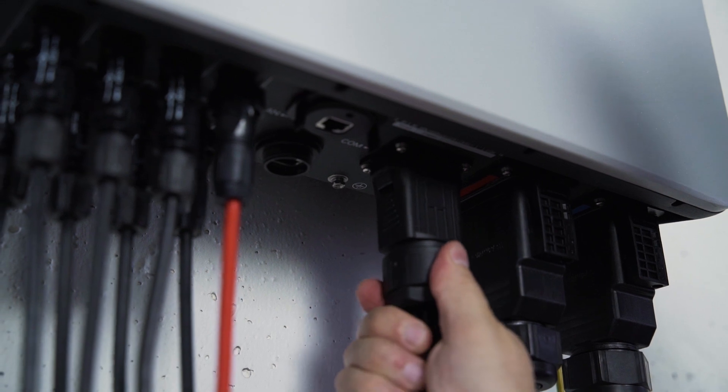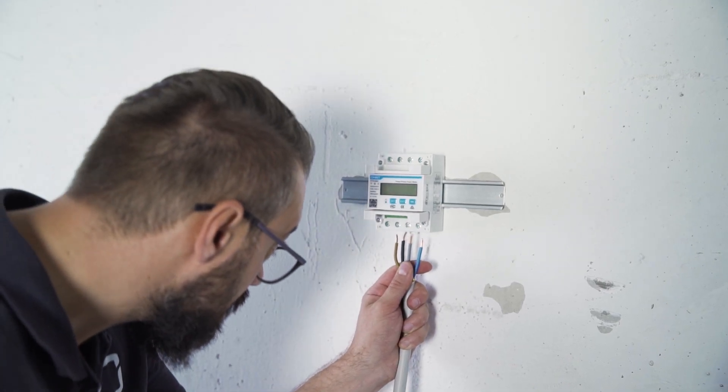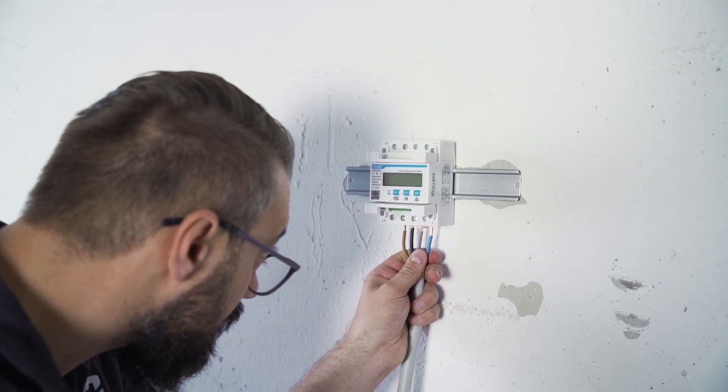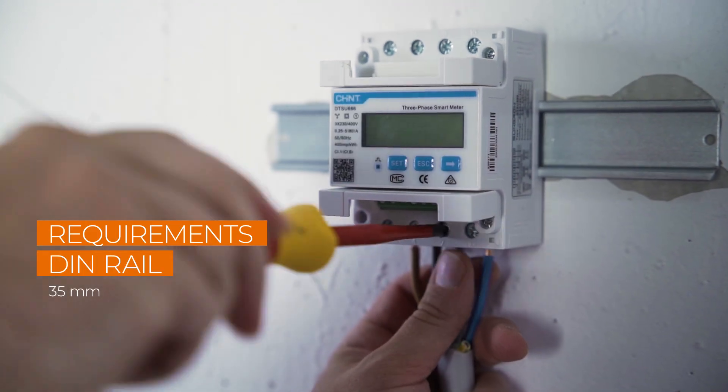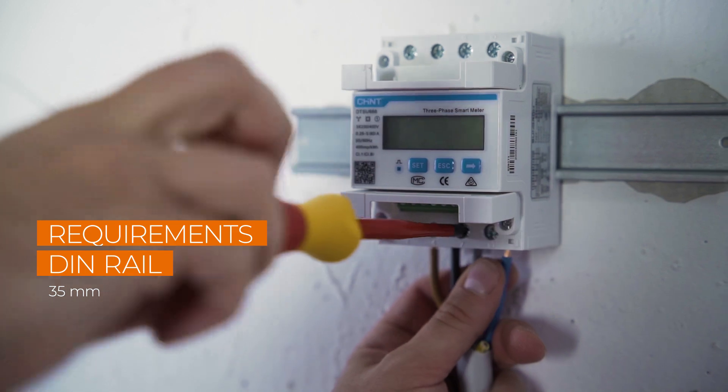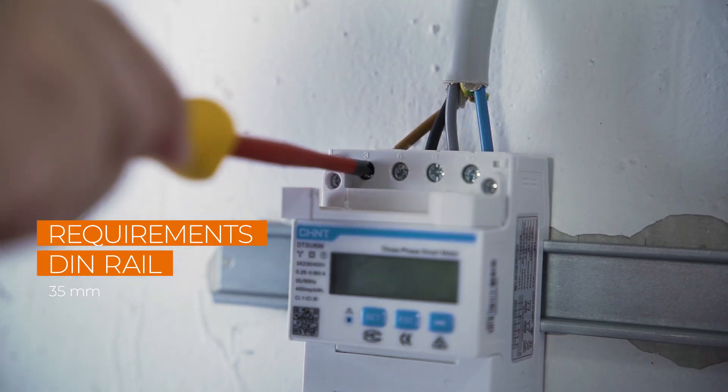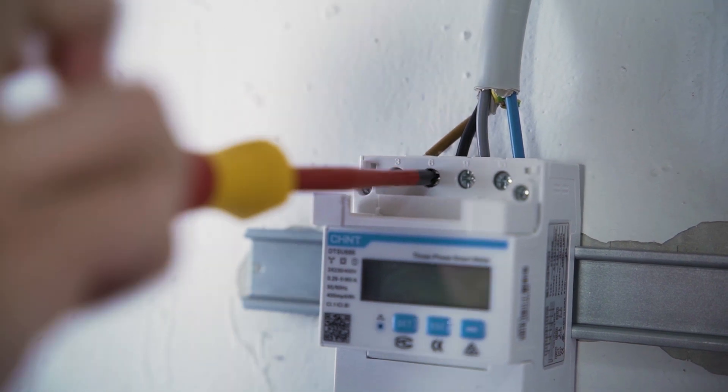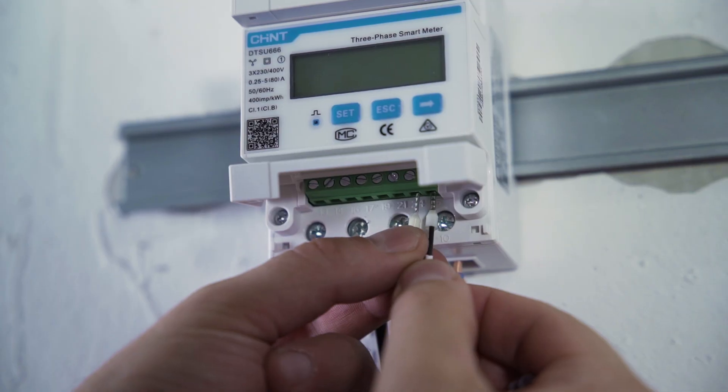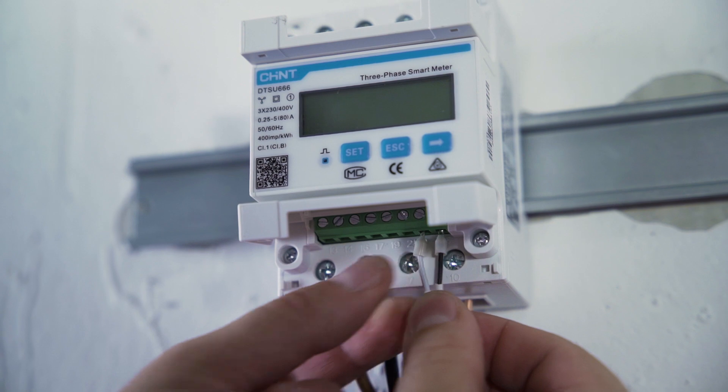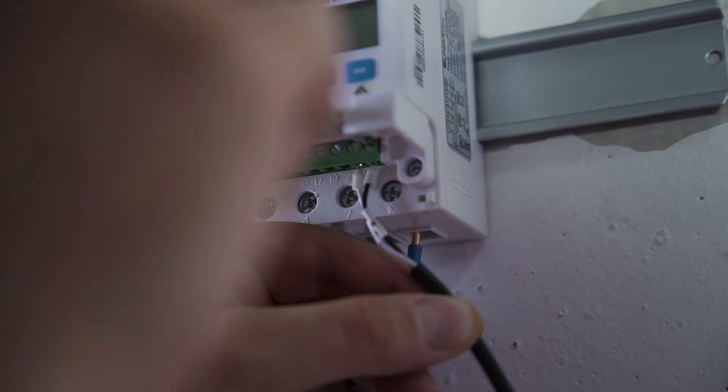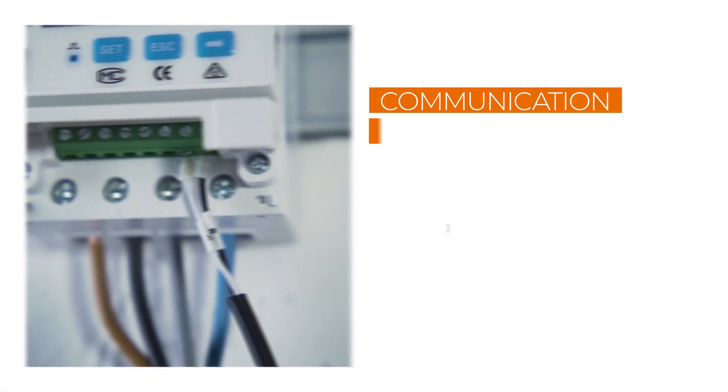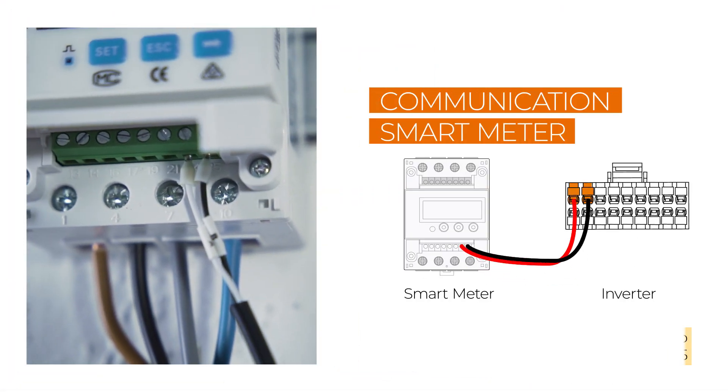To enable the inverter to use all functions, the smart energy meter must be connected. This is mounted on a DIN rail and then connected to the power cable. The power goes into the meter at the bottom and comes out at the top. The meter cable has already been connected to the inverter via the communication plug. Now it must be connected to the smart energy meter. For this you have to connect the cable to pins 24 and 25.